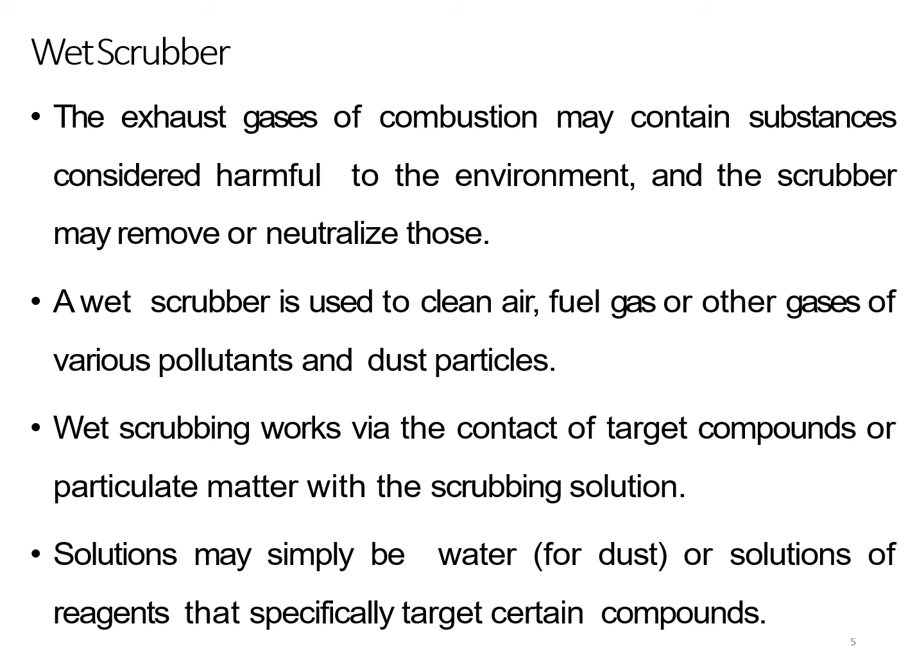The wet scrubbers are used where the exhaust gases of combustion may contain substances considered harmful to the environment, and the scrubber may remove or neutralize those. A wet scrubber is used to clean air, fuel gas or other gases of various pollutants and dust particles. Wet scrubbing works via the contact of target compounds or particulate matter with the scrubbing solution. The solutions may simply be water or solutions of reagents that specifically target certain compounds.